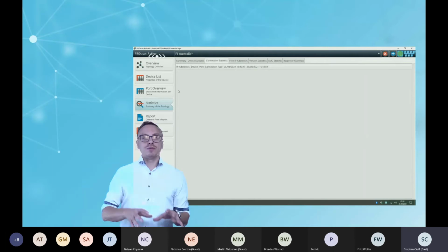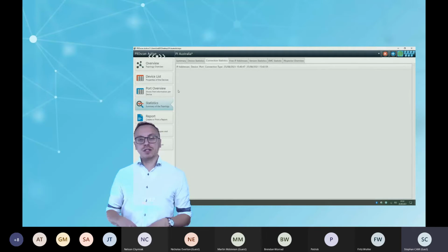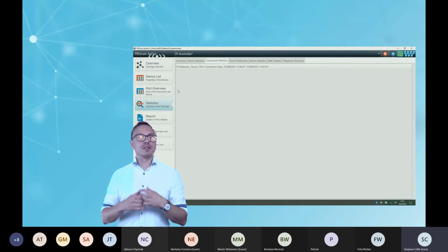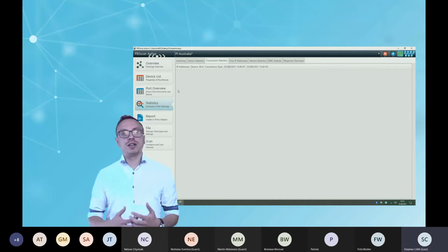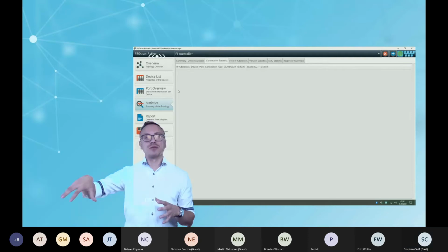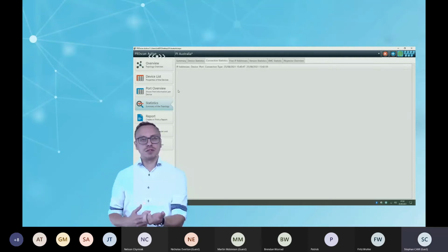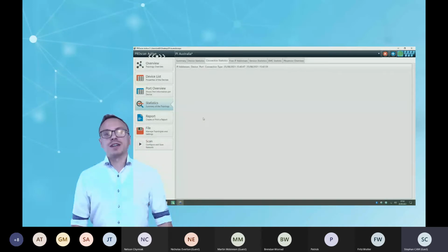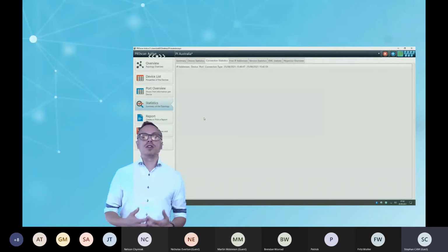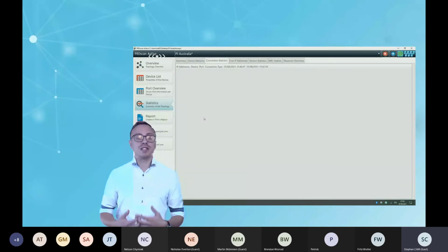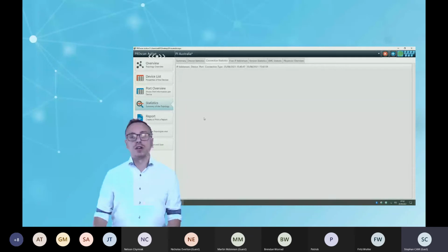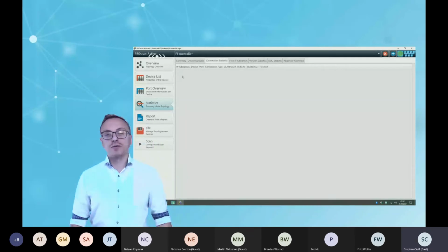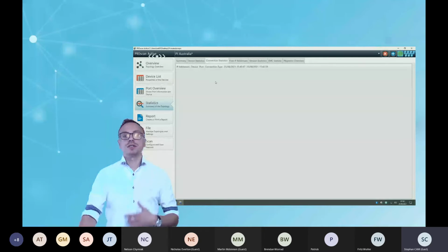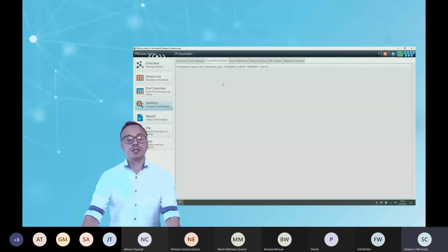PROFINET has a device diagnostic. So if you have problems with the device, you get a very nice diagnostic. But if you have network issues, you don't get a diagnostic. In this situation, the devices know they're discarding frames, but they don't send this information to the PLC. The software ProScan Active can analyze the system and ask all devices, did you discard frames, and how many frames did you discard on which port. So if you have discarded frames, you get here a table, and in this table you see which device, which port, and whether it's error frames or discarded frames. So is this because of overload, or is it because of some interference?